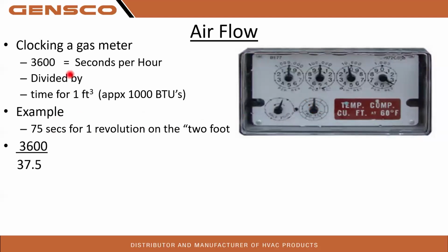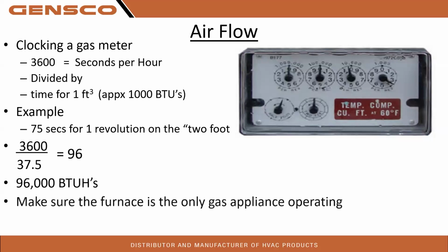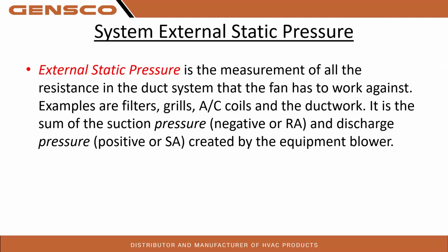So 3,600, that is a 2-foot dial, so we divide 75 by 2, which is 37.5. We take 3,600 divided by 37.5 equals 96. 96,000 BTUs we're producing in this example. So again, make sure the furnace is the only gas appliance operating. Then we can actually see how many BTUs we are putting out on a gas furnace, and the airflow.